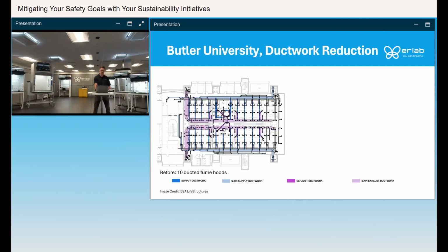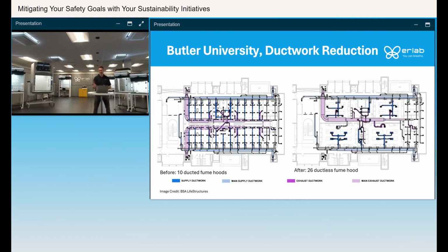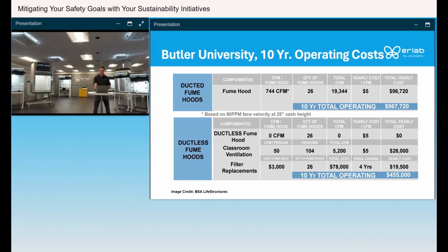After they installed the 26 ductless fume hoods and had the renovation, this is what the ductwork looked like. So it significantly simplified the amount of ductwork needed. And then since that was 2011, we do have 10-year operating costs. So they were changing the filters every 4 years.